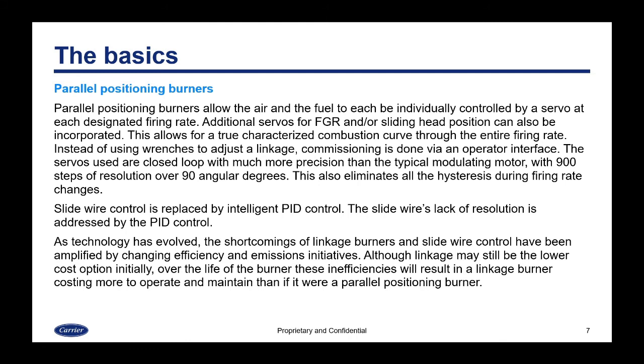Instead of using wrenches to adjust the linkage, commissioning is done with an operator interface. The servos used are closed loop, meaning there's feedback, with much more precision than the typical modulating motor, with 900 steps of resolution over 90 angular degrees. This also eliminates all the hysteresis or the slop during firing rate changes. Slide wire control is also replaced by intelligent PID control. The slide wire's lack of resolution is directly addressed by that PID control.